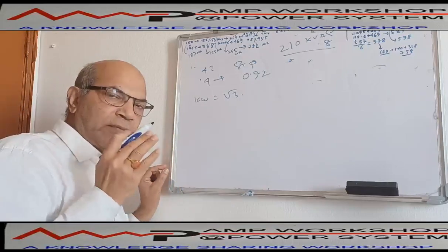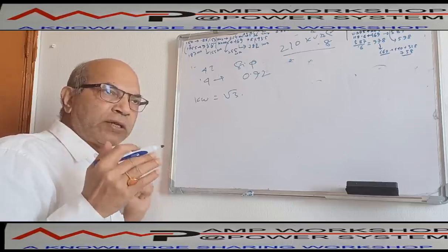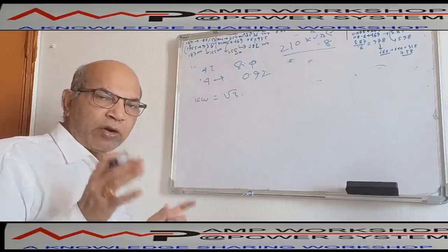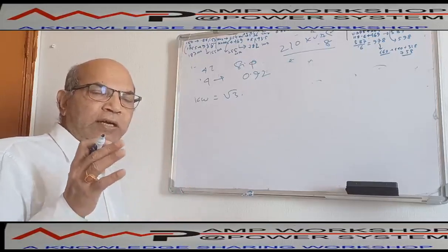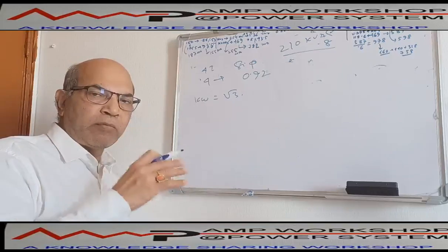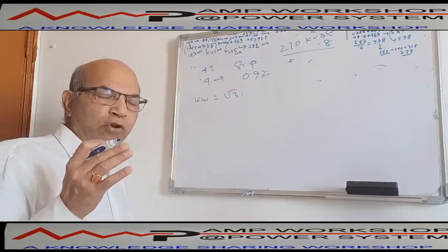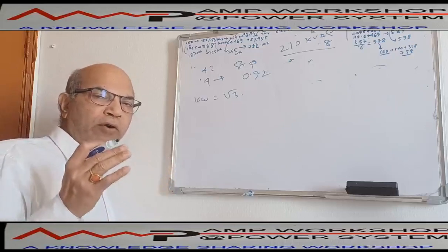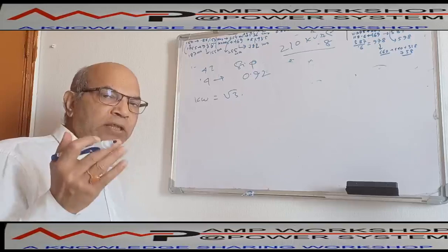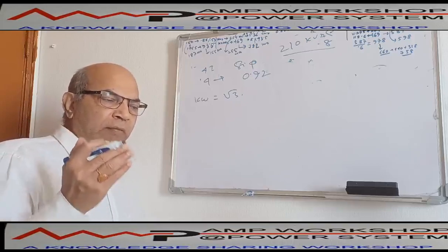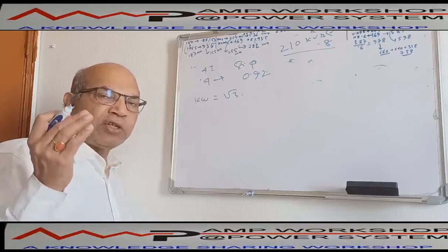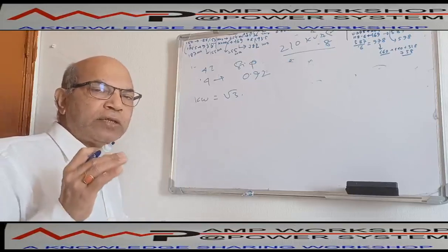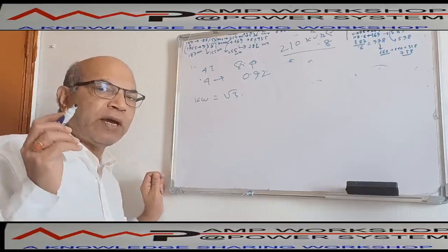We have talked about full voltage starting, but when the motor gets started it draws huge current, and there is a voltage drop in the cable. So though the generator voltage is full voltage, the motor terminal voltage will not be full. Motor voltage will be reduced. Generally we allow the motor to start at 80% of the voltage; in the motor specification we say the motor shall be started at 80% of the terminal voltage. But here we are keeping a 5% cushion in hand, so we will consider the motor to be started at 85% of the rated voltage.